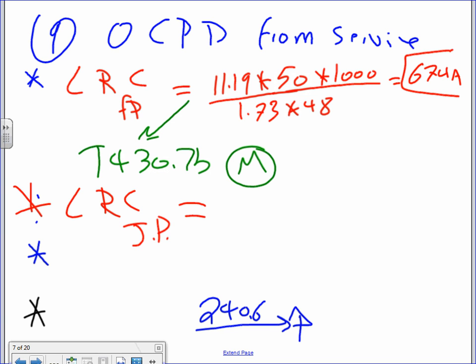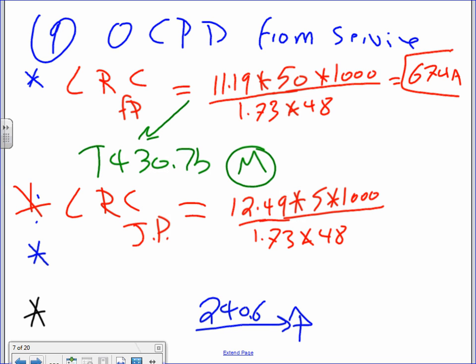Jockey pump. So the jockey pump, guys, what's the code letter for the jockey pump? The code letter is what? N. Based on N, it's a 12.49 multiplied. What's the horsepower, Matt? 5? Yep, thank you. 5 times 1,000 divided by 110. Oops. Divided by the whole 1.73 times 480. And that will get you a healthy 75 amp.